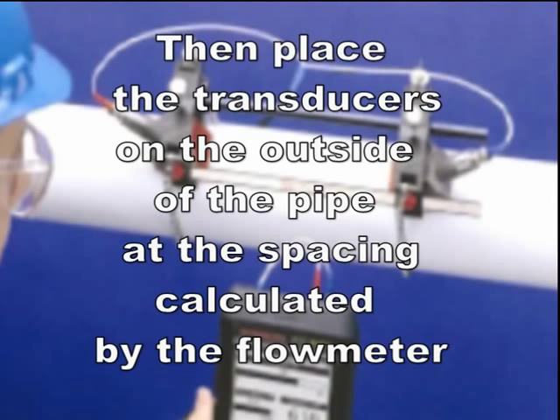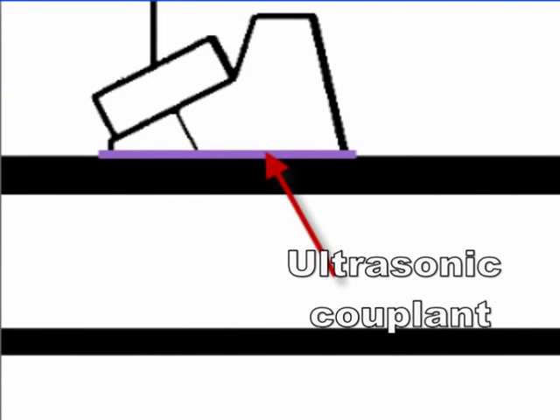We then place the transducers on the outside of the pipe at the spacing calculated by the flow meter. We also need to place an ultrasonic couplant between the transducers and the pipe, because an air gap will stop the ultrasonic signal.